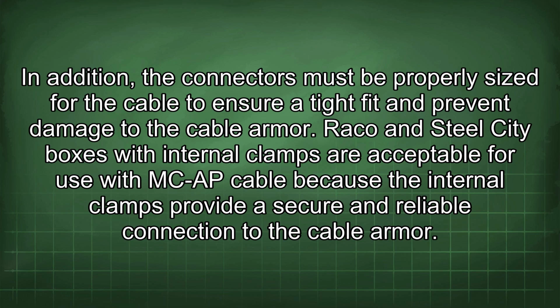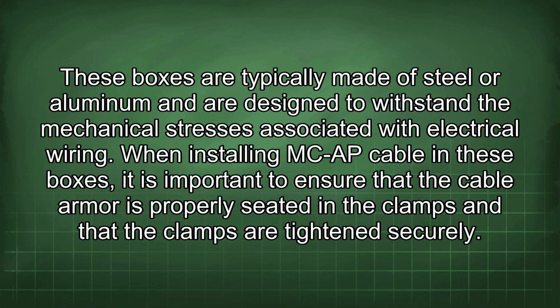the cable armor. Raco and Steel City boxes with internal clamps are acceptable for use with MC-AP cable because the internal clamps provide a secure and reliable connection to the cable armor. These boxes are typically made of steel or aluminum and are designed to withstand the mechanical stresses associated with electrical wiring. When installing MC-AP cable in these boxes, it is important to ensure that the cable armor is properly seated in the clamps and that the clamps are tightened securely.